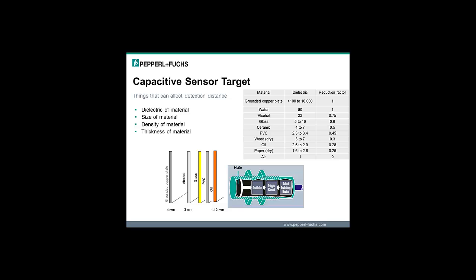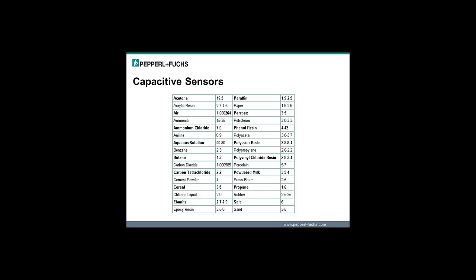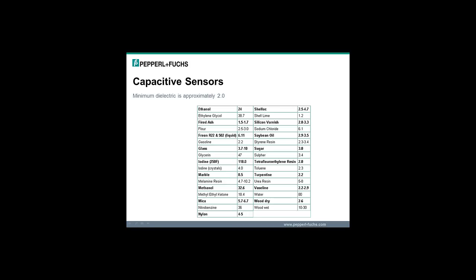As mentioned earlier, the dielectric, size, density, and thickness of the material may have an effect on the detection distance. If the dielectric of the material is less than metal or water, there will be some reduction factor for that material. If we have a CBB4-12GH60-E2-V1, the sensing range for grounded copper plate and water is approximately 4 millimeters. But if we try to detect oil with a dielectric of 2.9, the sensing range would be approximately 1.12 millimeters. The dielectric chart on this page and the following pages show the dielectric for common materials. Here are a few materials with their dielectric listed. The minimum dielectric necessary for a capacitive sensor to detect a material is approximately 2.